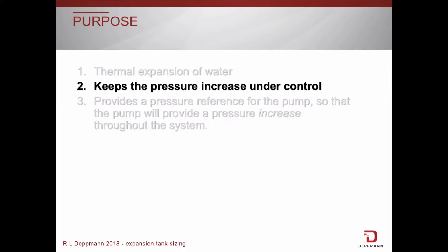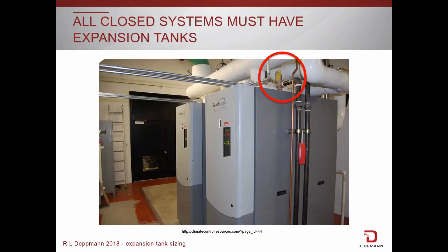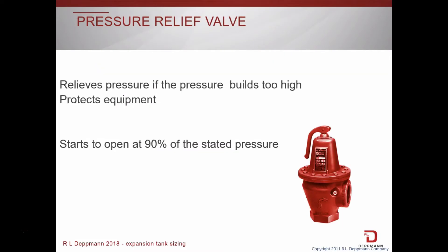One of the purposes of the expansion tank is to keep the system's pressure under control. In other words, it's the tank's job to keep the relief valve from opening. So let's start by discussing relief valve pressures. The main purpose in the life of a pressure relief valve is to relieve system pressure if that pressure starts to build too high.